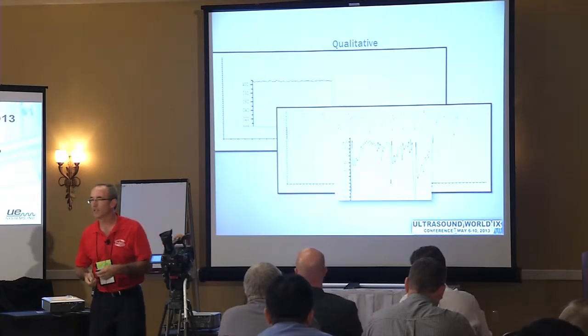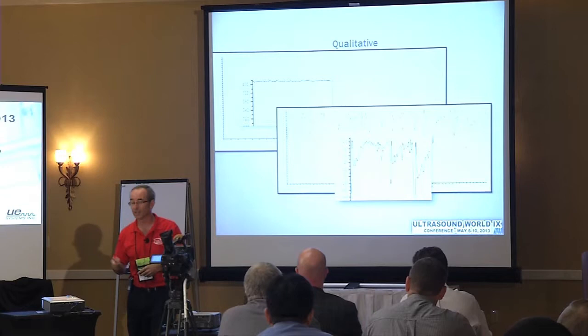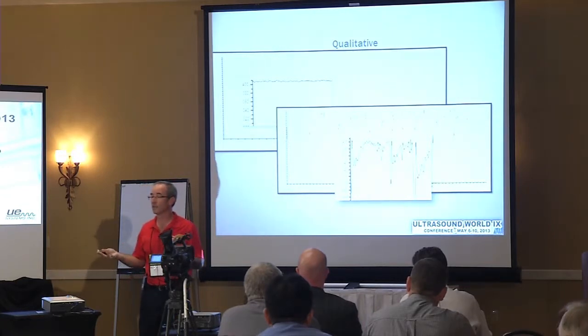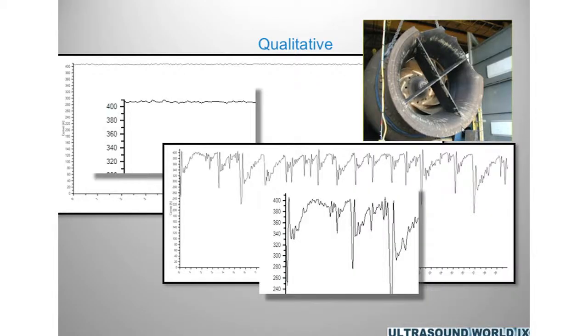Let's bring in the guys that know the mechanics and say, hey, we've got something going on here. In this situation it's very likely going to be, in fact I think there's a picture of it, cavitation. With the bell broken on this pump, it was creating a severe torque change as a result of cavitation.